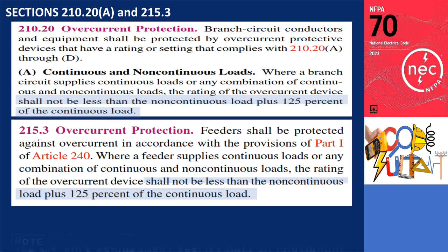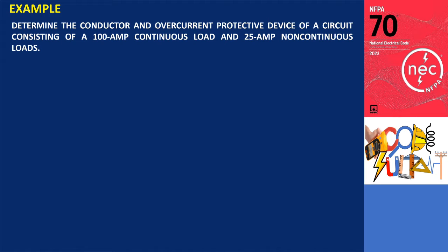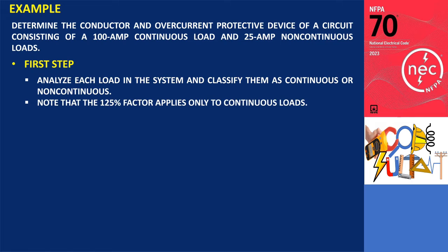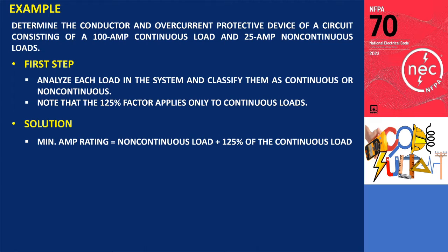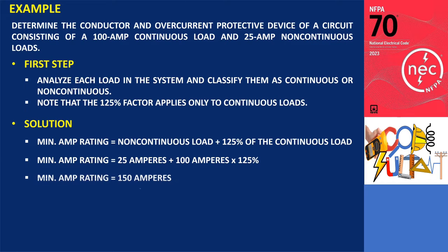It is important to note that the 80% rule requirement applies only to continuous loads. Let's have an example. Determine the conductor and overcurrent protective device for a circuit consisting of a 100A continuous load and a 25A non-continuous load, with correction and adjustment factors of 100%. Referring to Section 210.20A, the 125% factor applies only to continuous loads. The calculation is: non-continuous load plus 125% of the continuous load. Therefore, 25A plus (100A × 125%) equals a total of 150A.